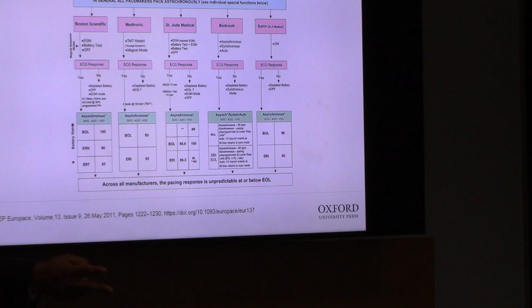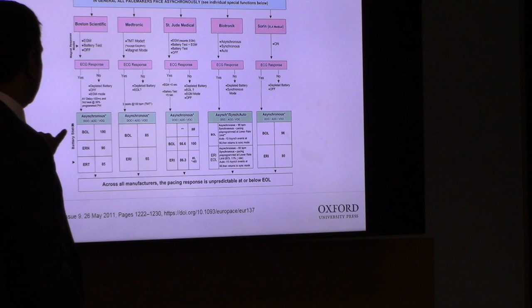And basically, the magnet won't make the device keep beeping all the time, so you know that it's appropriately placed. So the first time you place it, you have to ensure that you're placing it right over the device, and you hear that long tone, you're fine. If you move that later, you might not know that you made that mistake. So I would recommend taping it, if possible, to that location.